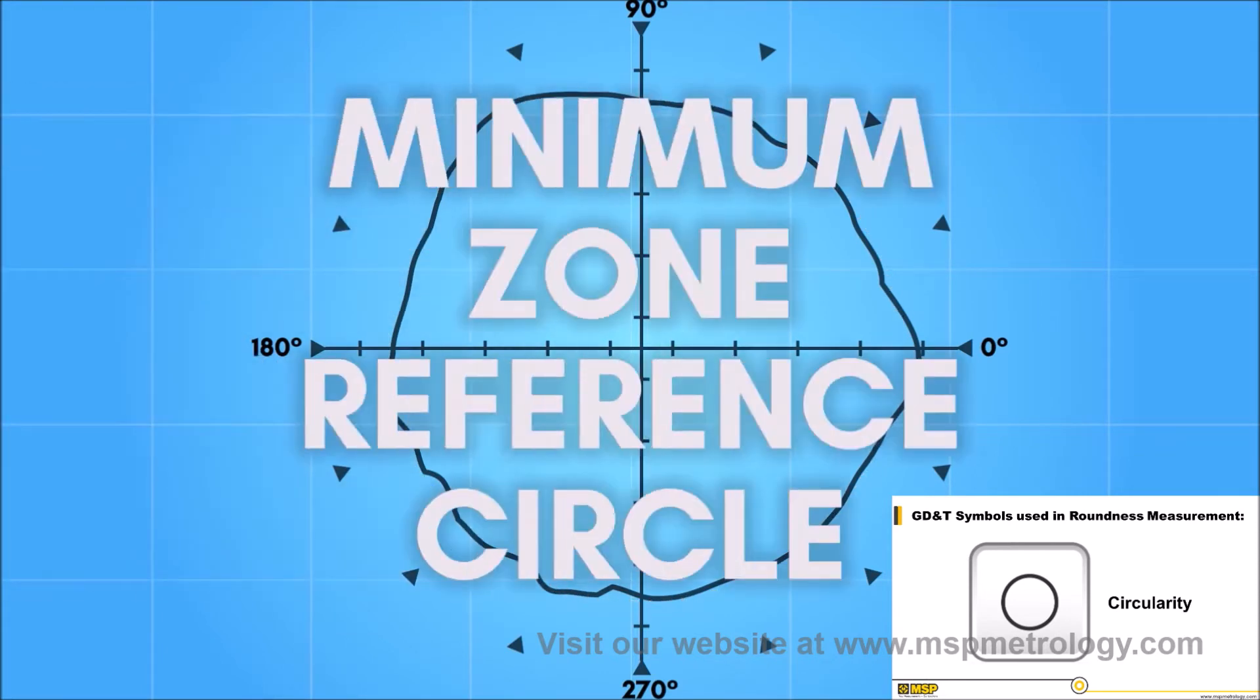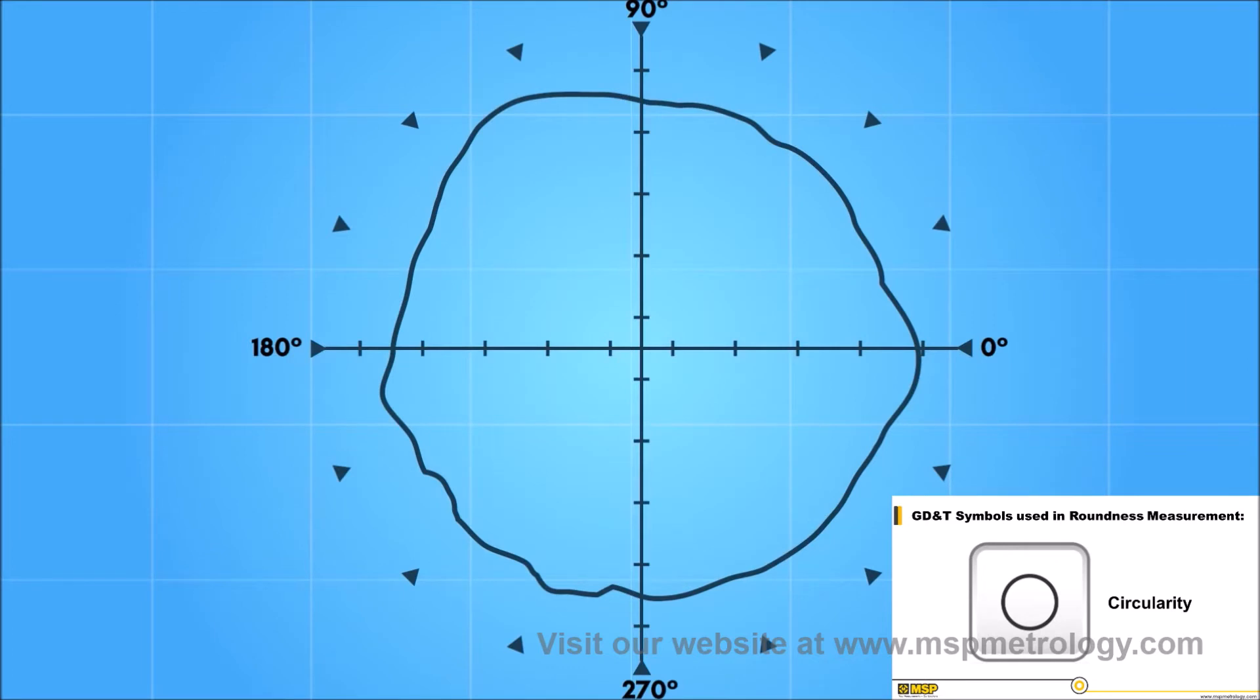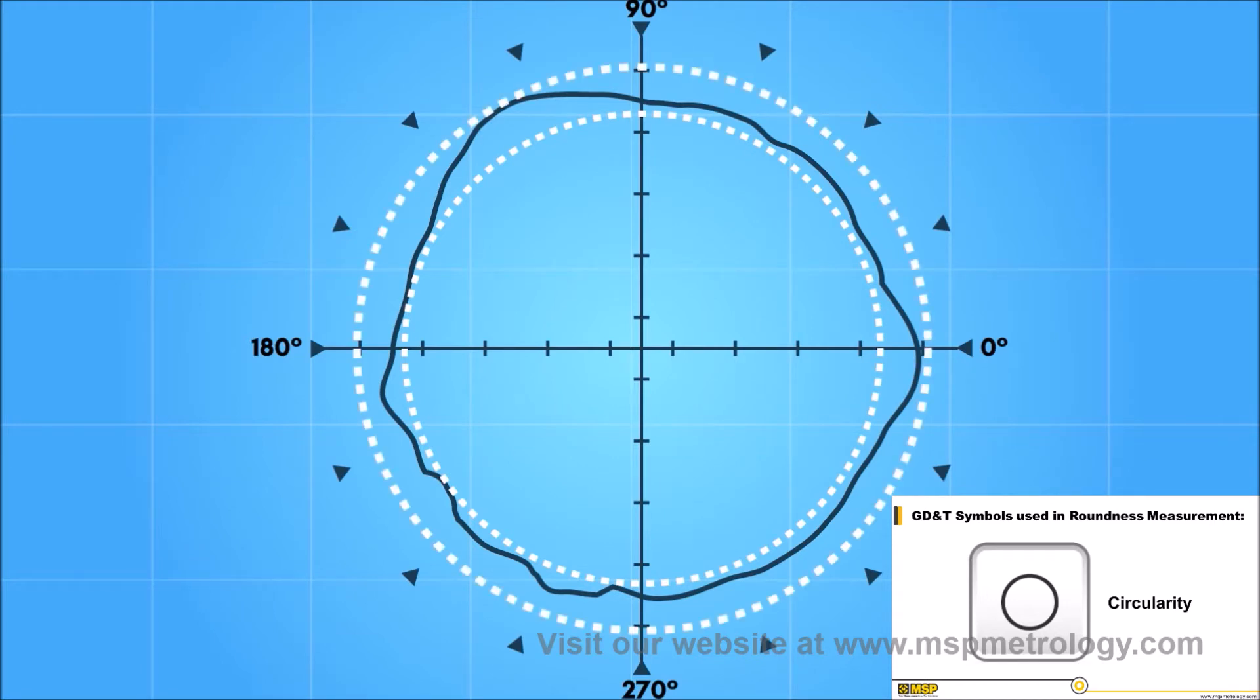A minimum zone reference circle is derived by first calculating the largest circle that can fit inside of the measured data. Next, the smallest circle that can encompass the measured data is calculated. The out of roundness is given by the radial separation between these two circles that enclose the data.